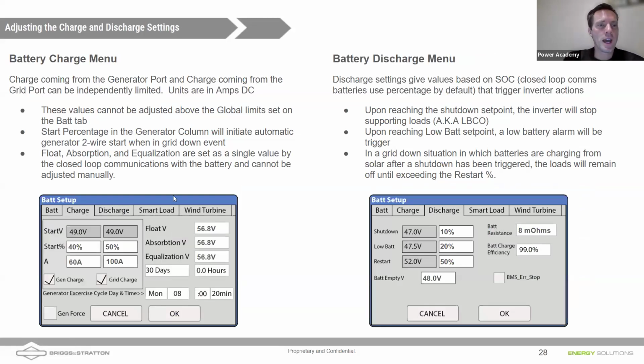Now, if we go to the charge tab of the battery setup on a Sol-Ark, what you will see is independent columns for using generator charge or grid charge to charge your batteries. So if you'd like to enable either of those, or if you've got AC coupled solar coming in through the gen port, you would want to have this box here checked for gen charge. The start percentage is going to be that value if the batteries drop below that value and you have an available charging source.